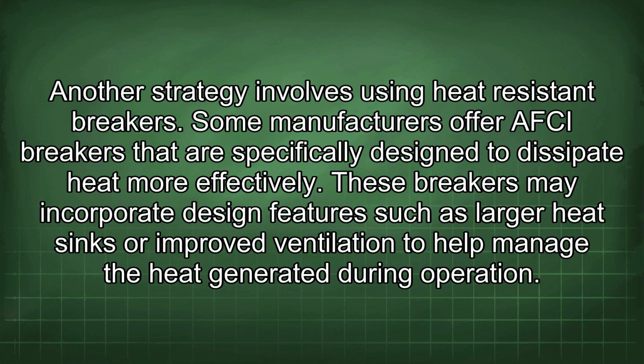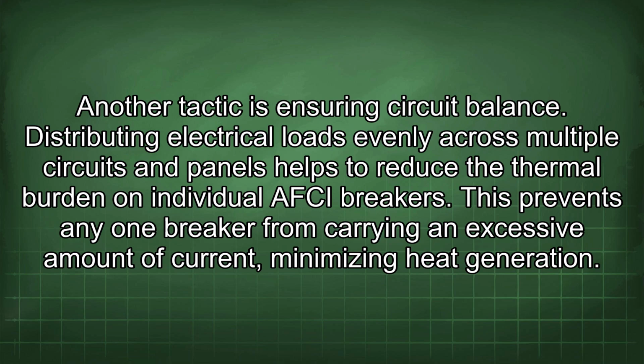Another strategy involves using heat-resistant breakers. Some manufacturers offer AFCI breakers that are specifically designed to dissipate heat more effectively. These breakers may incorporate design features such as larger heat sinks or improved ventilation to help manage the heat generated during operation. Another tactic is ensuring circuit balance. Distributing electrical loads evenly across multiple circuits and panels helps to reduce the thermal burden on individual AFCI breakers. This prevents any one breaker from carrying an excessive amount of current, minimizing heat generation.